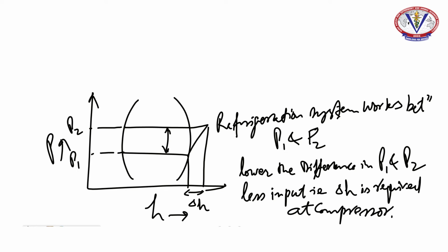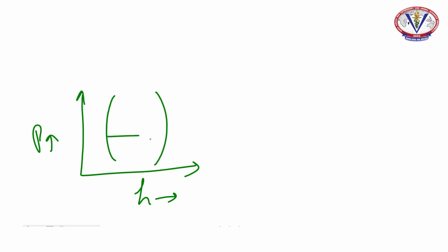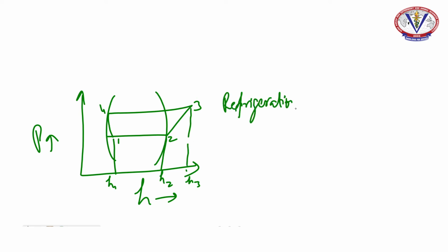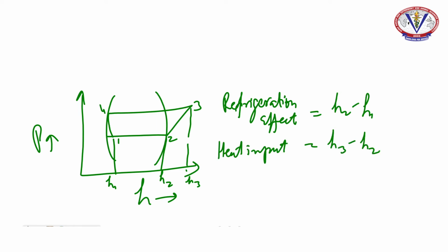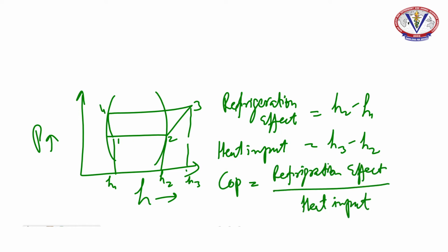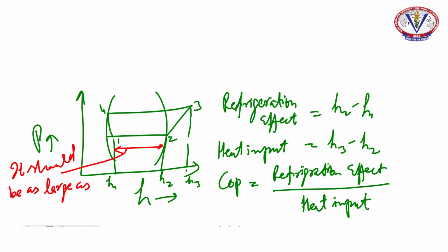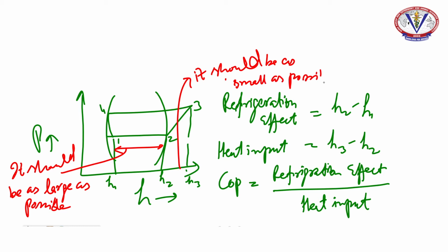There is a term called coefficient of performance or COP, which is a measure of efficiency of the refrigeration system, defined as the ratio of refrigeration effect produced to the energy input. So the higher the refrigeration effect and the lower the energy input, the higher the COP will be. So the whole effort while designing the basic refrigeration systems is to get as large a refrigeration effect as possible with as little input energy as possible during the compression process.